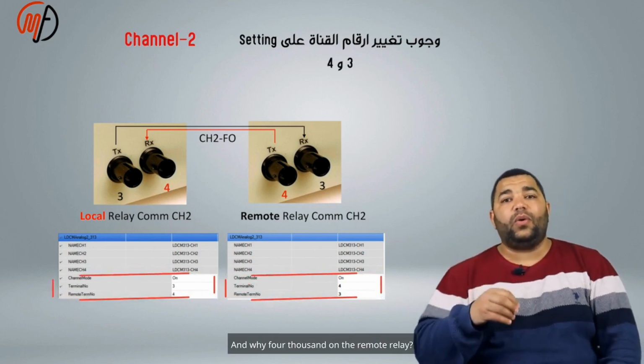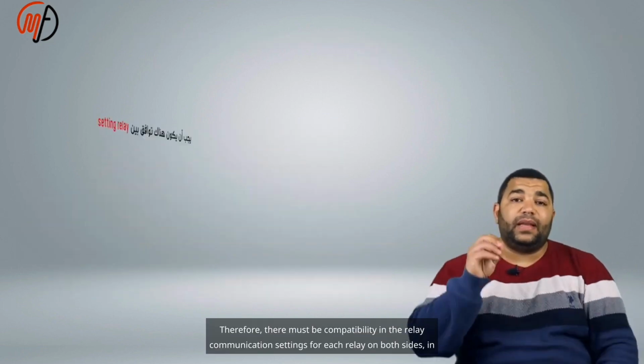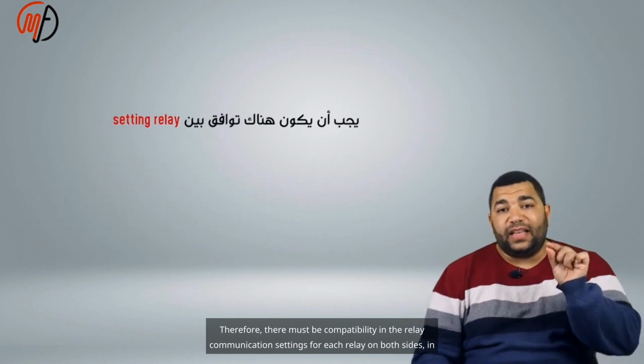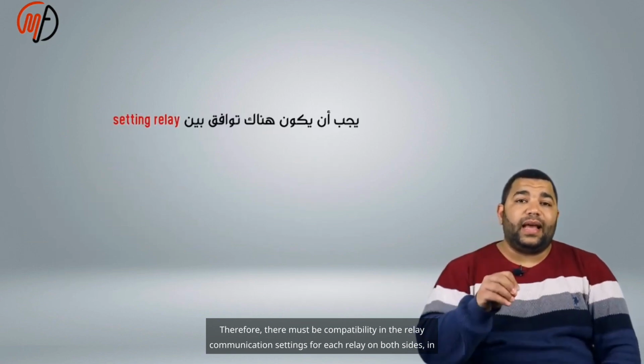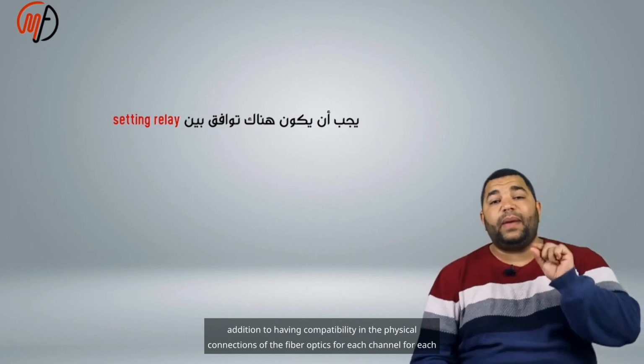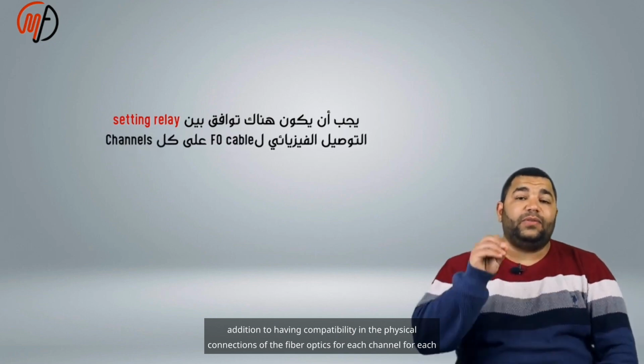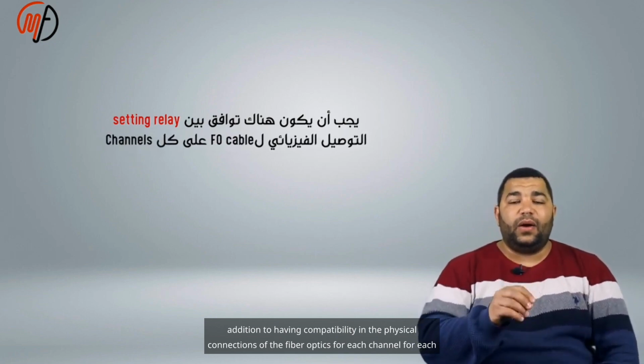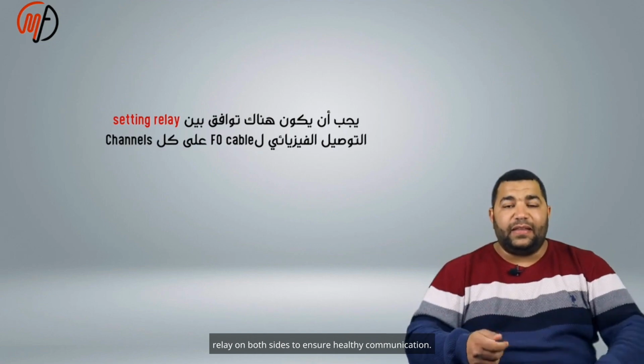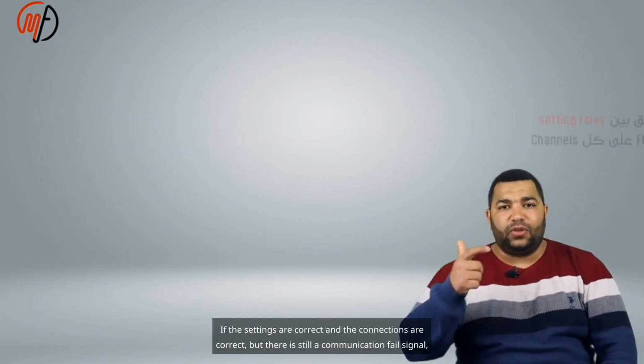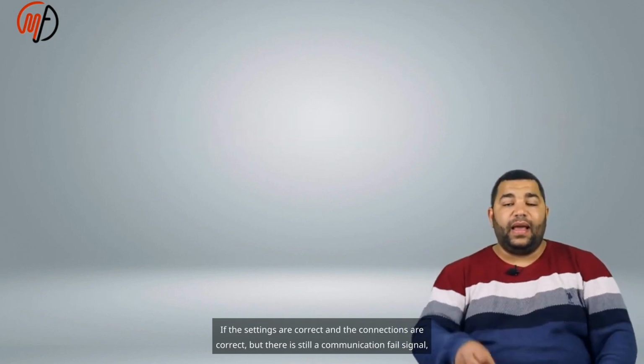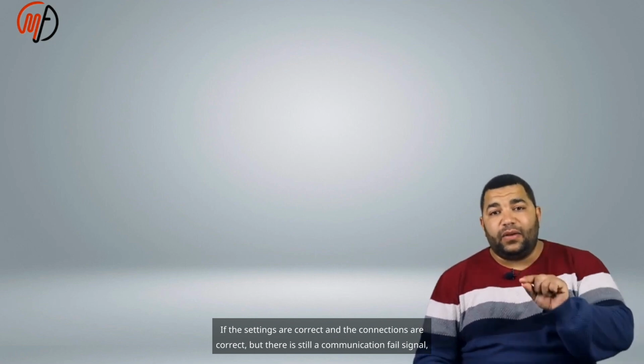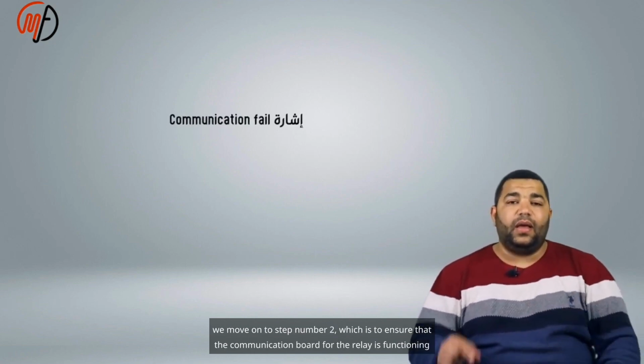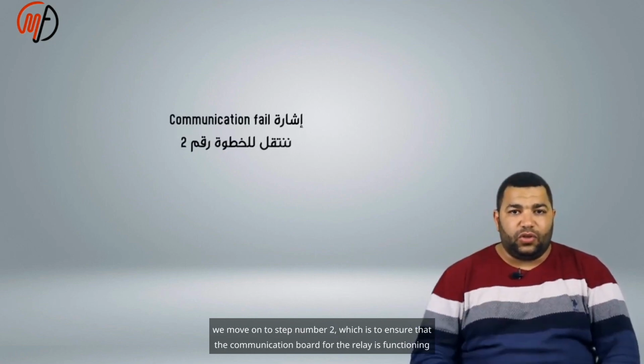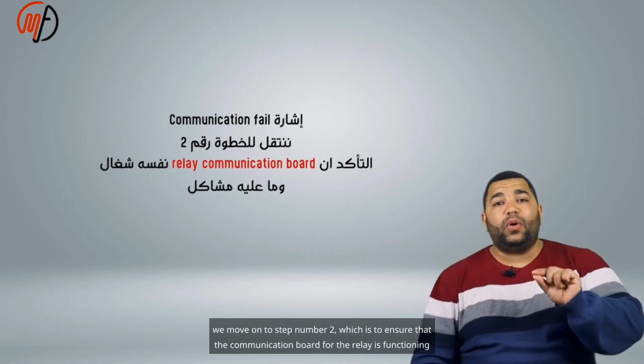And why 4 on the remote relay? Therefore, there must be compatibility in the relay communication settings for each relay on both sides, in addition to having compatibility in the physical connections of the fiber optics for each channel for each relay on both sides.